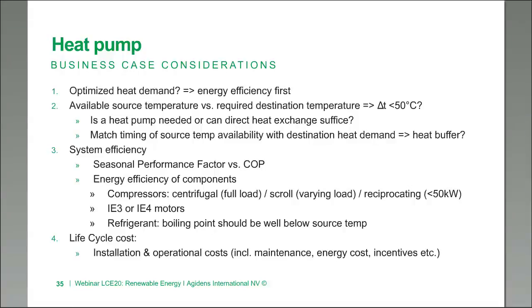The first thing is to really look at the demand and optimize that. Once you've done that, you can look at which source temperatures you have available versus the required destination temperature you need. If you have temperature differences less than 50 degrees centigrade, then heat pumps are very much an applicable technology. Having said that, in some cases you may not even need a heat pump. If you look at the total heat balance within your company, you may perfectly have a waste stream that is actually higher in temperature than some other heat demand needs — for those applications you can just use a direct heat exchanger without needing to upgrade the waste heat even further.